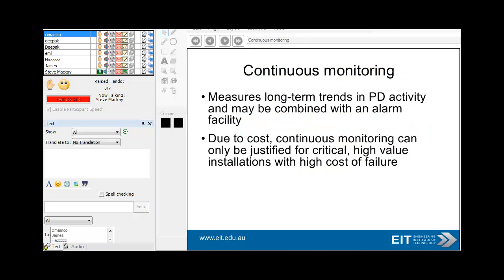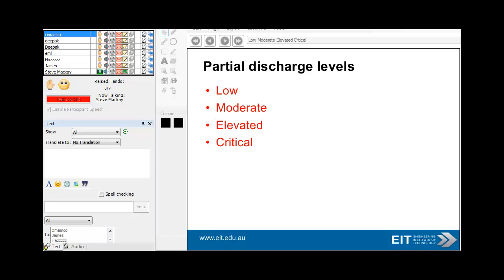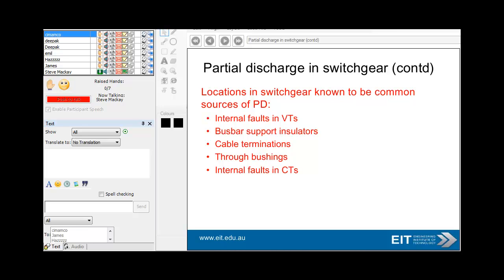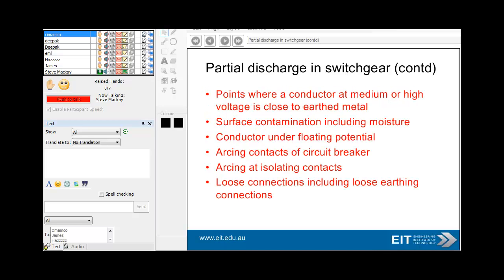Partial discharge monitoring is useful for older installations. Continuous monitoring allows you to look at long-term trends, but can only really be used for expensive, high-value or strategically important installations. Partial discharge levels can range from low all the way through to critical. Locations where you get partial discharge include internal faults in VTs and PTs, voltage transformers, bus-bar support insulators, cable terminations, bushings, and internal faults in CTs and grounding transformers. Points where conductors at medium or high voltage are close to earthed metal, and surface contamination, are always potential problems.